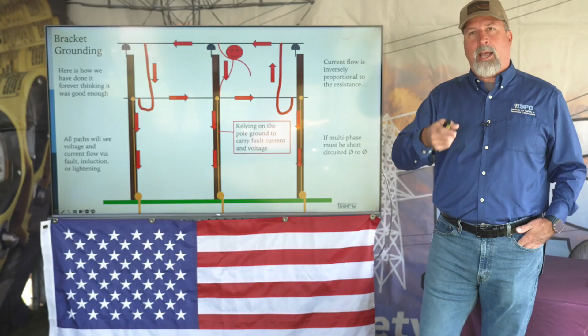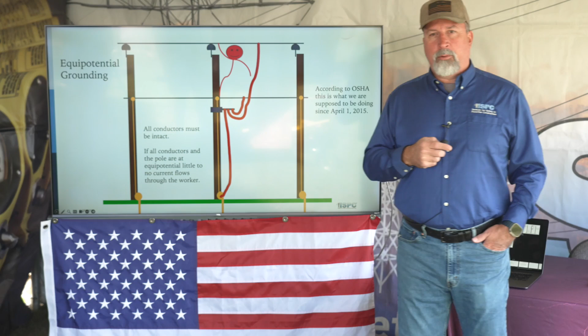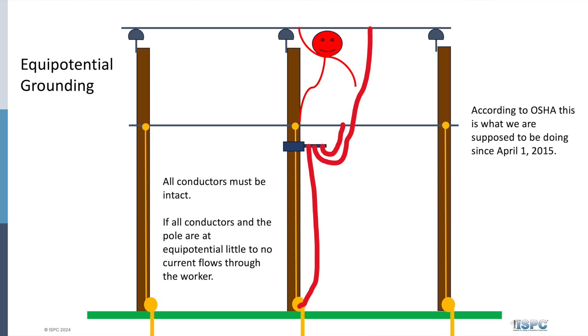So there's multiple ways to skin this cat, but you got to be aware, and you got to understand what the risks are and what the potential hazards are, so that you can make the best choice of how to protect yourself. Since 2015, we've been required by OSHA to install our grounding and bonding in an equipotential fashion. Again, in order to do this, all your conductors have to be intact. If you have broken conductors, you can't equipotentially ground at that point. So we just need to understand that.